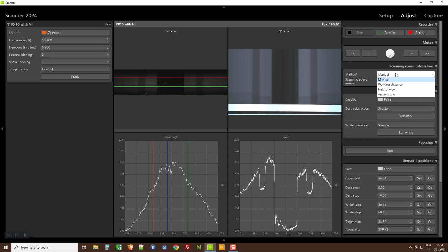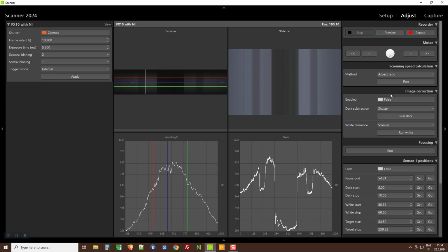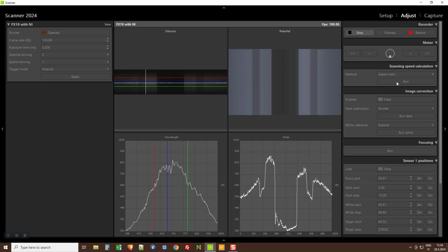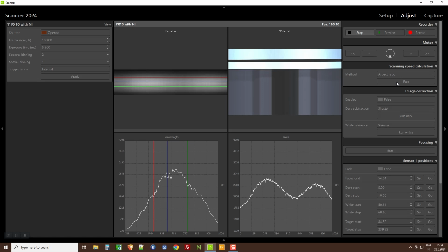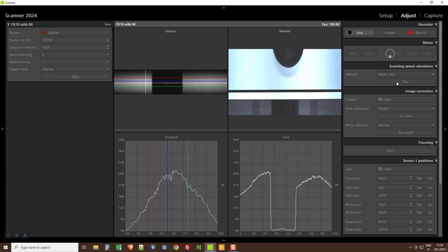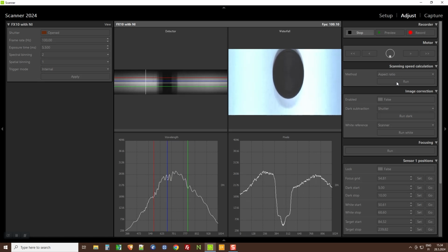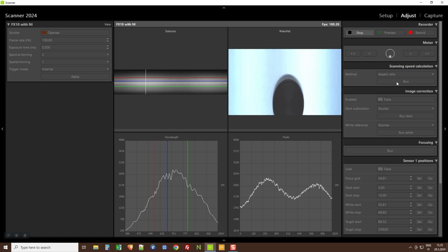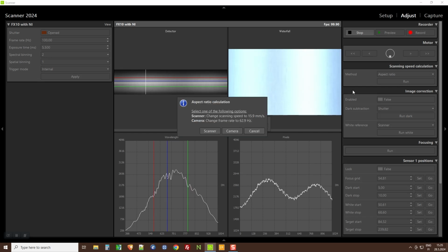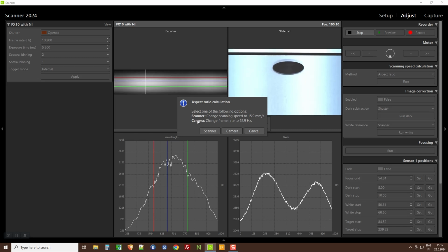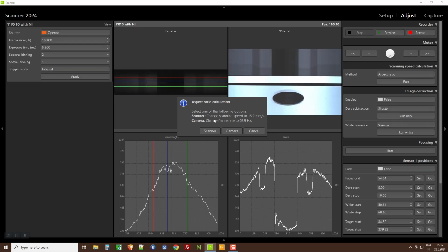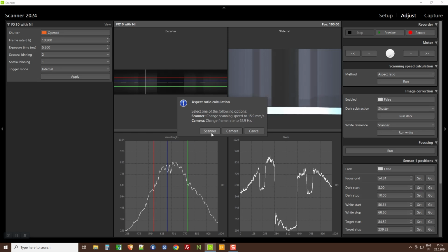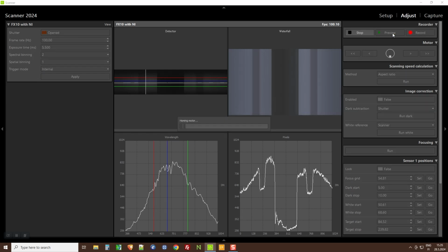Notice that if you want to find the optimal speed, you can try different ones manually, or there is something called aspect ratio, and then you can click on it, and automatically the system will propose you an optimal scanning speed. So to do that, you need to put something dark and round at the top of something white, or the opposite, a white round at the top of a black support, and then it will compute for you what is the correct speed to have a correct aspect ratio. So here it proposes either to change the scanning speed or the camera acquisition speed. So here I would change the scanning speed. Then we can try again with a preview.